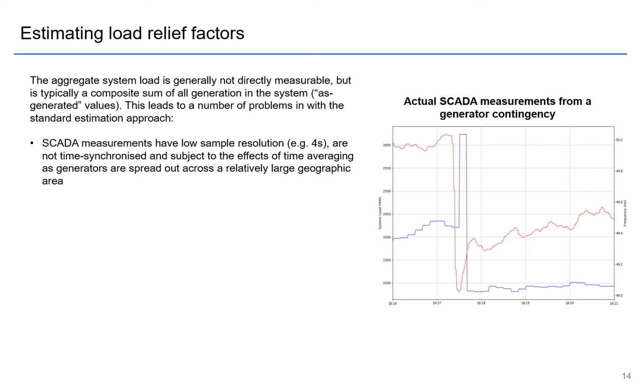One of the main issues is that the polling rate of different generators is different. Some generators are polled every 4 seconds and give you a very accurate reading every 4 seconds. Other generators will give you a reading every 30 seconds or every minute. So the as generated values are not very accurate at sub 4 seconds or even sub 1 second resolutions. Yet that's what we want when looking at a frequency disturbance. We need sub-second, or at least 1 second, readings of load against frequency, because the disturbance is all over by the first 10-15 seconds.